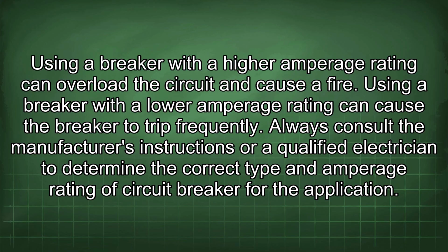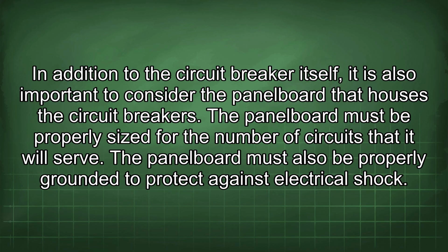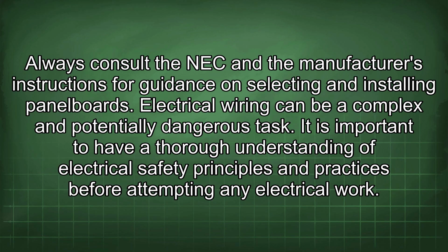In addition to the circuit breaker itself, it is also important to consider the panel board that houses the circuit breakers. A panel board must be properly sized for the number of circuits that it will serve. The panel board must also be properly grounded to protect against electrical shock. Always consult the NEC and the manufacturer's instructions for guidance on selecting and installing panel boards.